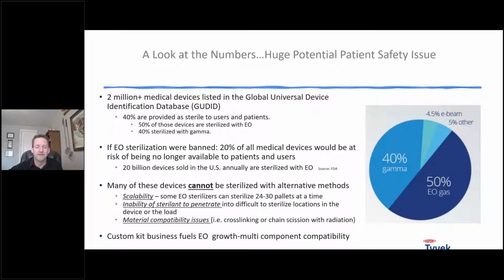We're talking 20 billion devices just in the US every year that are sterilized with ethylene oxide. 20 billion devices. And many of these devices can't be sterilized with alternative methods. We'll talk a little bit about some of the methods that were proposed. Really, there's three main reasons why there's not another type of sterilization that can just come in and replace ethylene oxide. One is scalability. Some of these EO sterilizers can sterilize up to 30 pallets at a time. You're talking a tractor trailer, a huge truckload of product in a chamber. And so, just enormous scale.